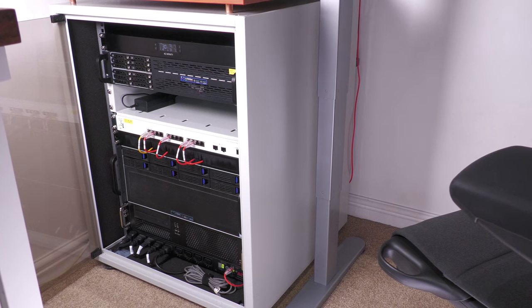I think the only thing I might need to do is at certain times of year, say in winter when it's a bit colder inside, I might need to adjust the set threshold, because currently I set it so that all day basically it can go between say 30 and 32 degrees inside the rack and the fans will stay on speed 1, which is what I want. And all day today it's basically done that.